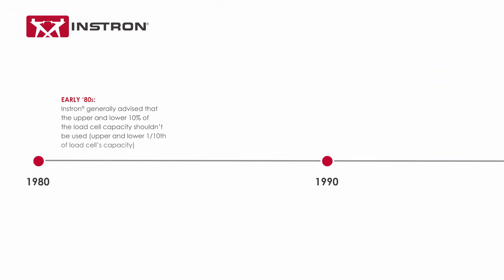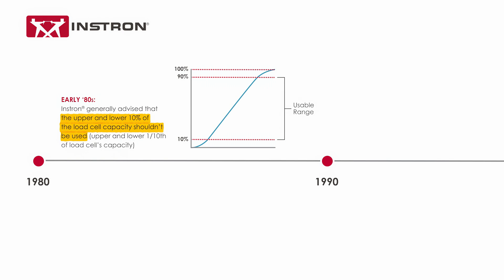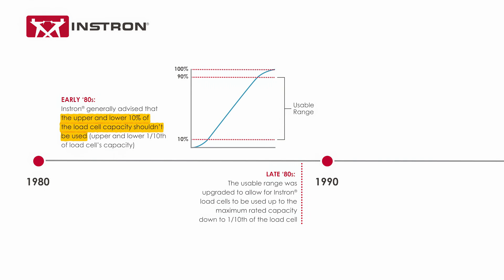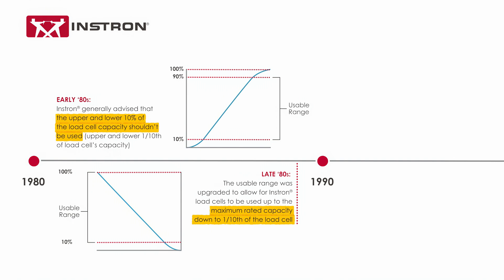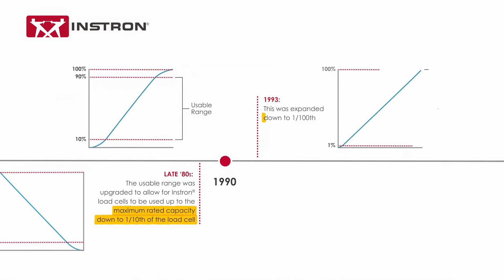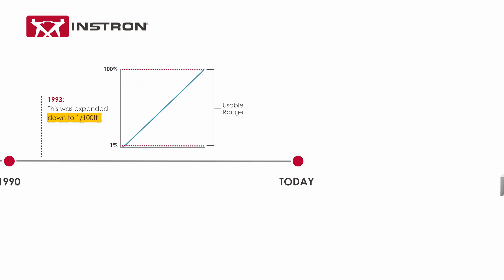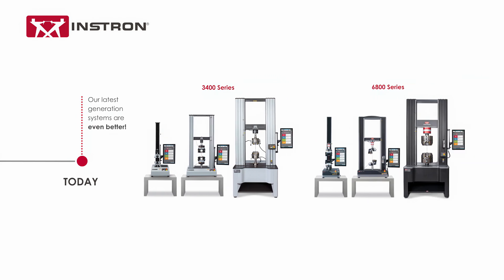In the early 80s, Instron generally advised that the upper and lower 10 percent of the load cell capacity shouldn't be used, meaning the upper and lower one-tenth of load cell capacity. But as the technology in our testing systems improved, this guidance has changed. In the late 80s, the usable range was upgraded to allow for Instron load cells to be used up to the maximum rated capacity down to one-tenth of the load cell. In 1993, this was expanded down to one one-hundredth, and now our latest generation systems are even better.